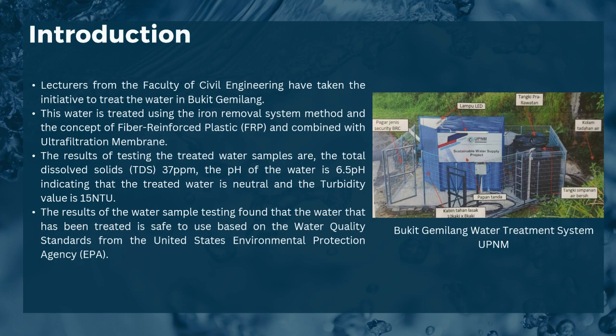The water is treated using the iron removal system method, combined with the concept of Fiber Reinforced Plastic (FRP) and ultrafiltration membrane. From the testing of the treated water samples, the Total Dissolved Solids (TDS) is 37 ppm and the pH of the water is 6.5.